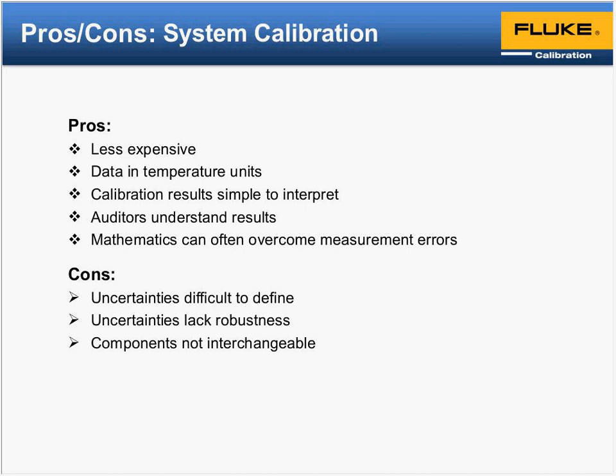So again, if you look at most calibration on a recalibration type situation, a set of data says as found, you sometimes can see in or out of tolerance, and adjustments are made, and then there's another that mirrors the incoming data, the as left levels. If we were to create a calibration run, we would show the as found of 100, and the 0.2 uncertainty. We would have to have a statement of these at 0.2 uncertainty, and then we would have the unit under test, and then what the tested as left.